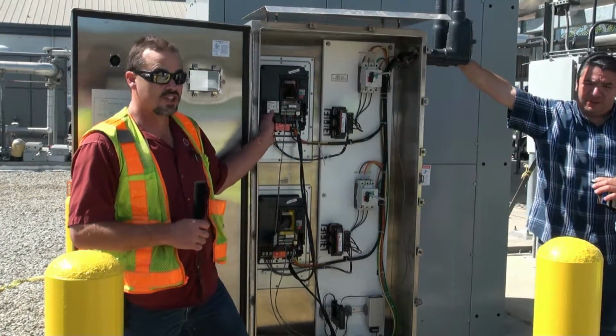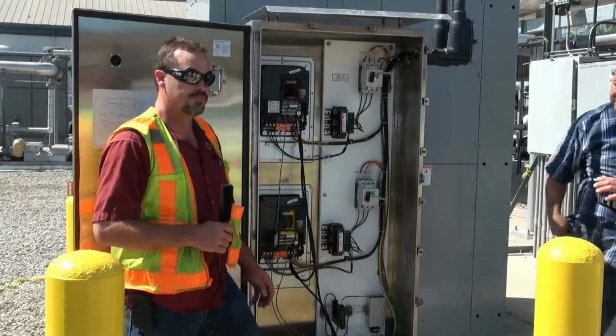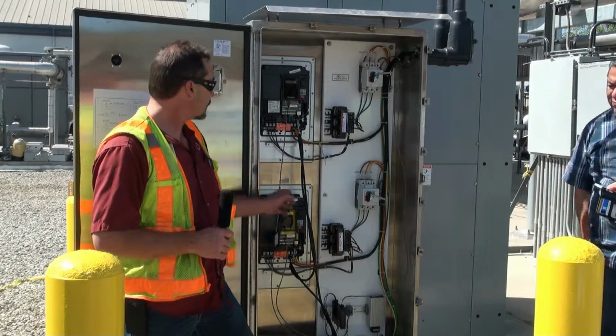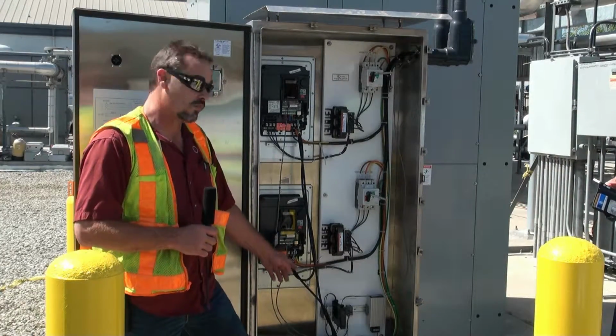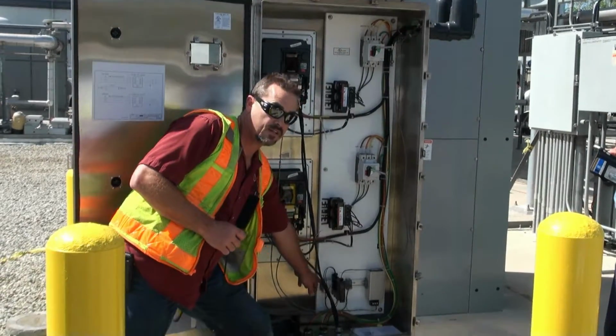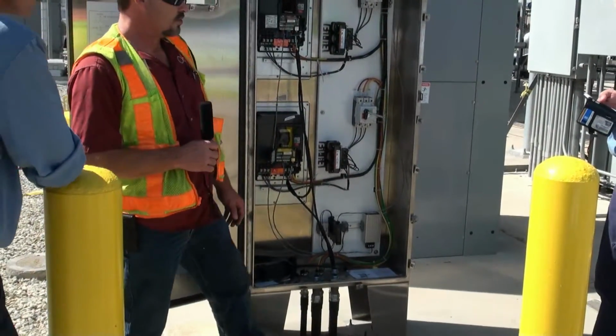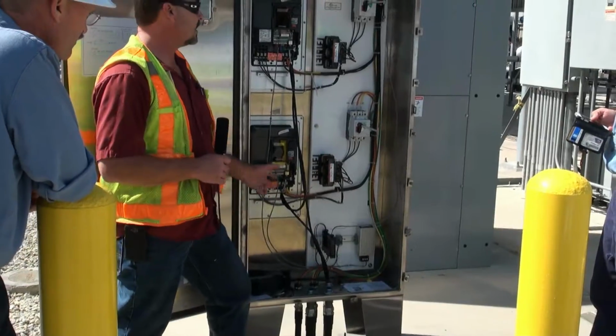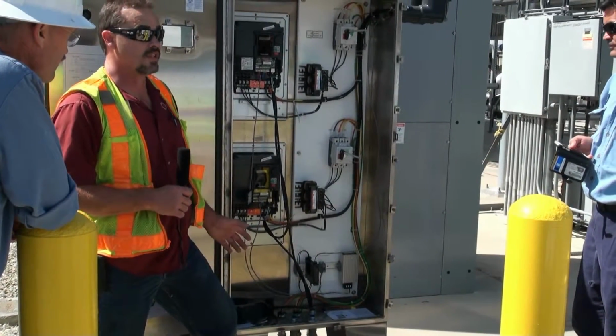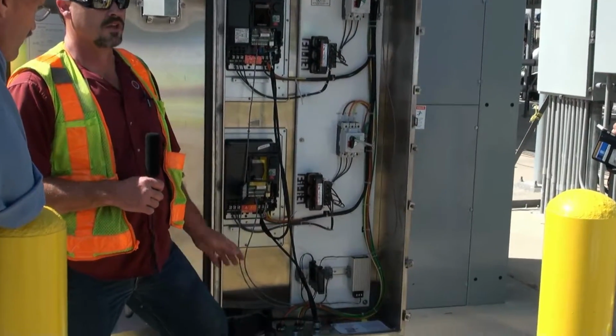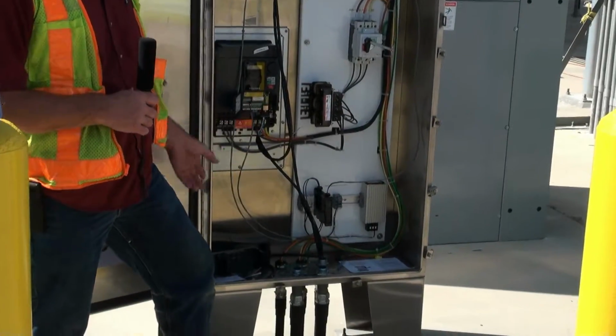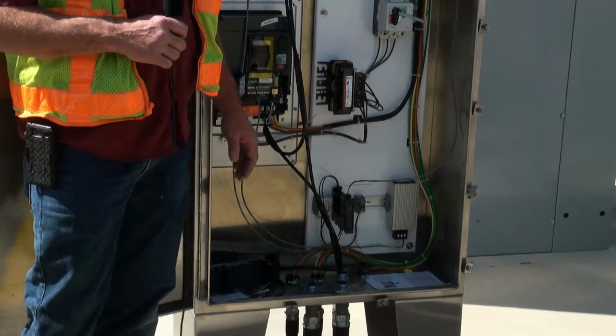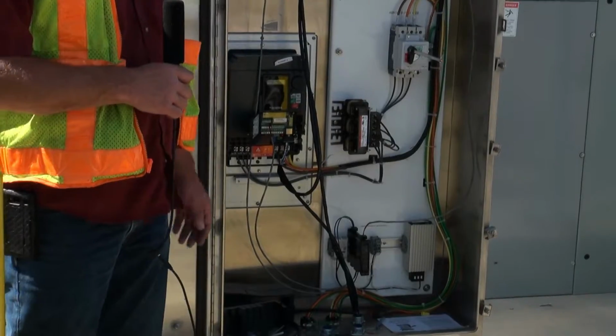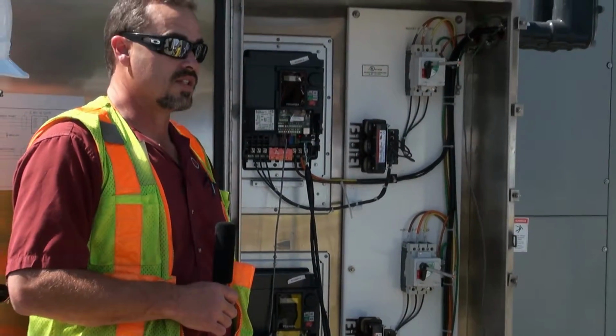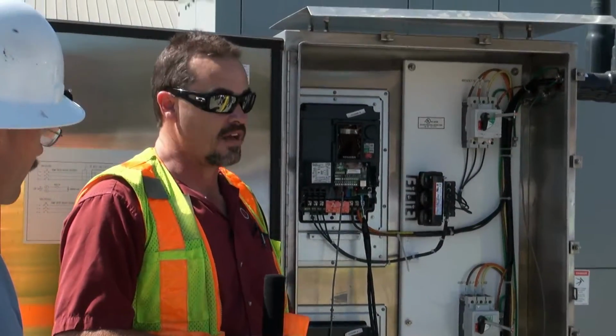Okay, so these are the Toshiba drives that we were talking about earlier. What we have to start with is we have a temperature sensor down here. Usually you want to have that set to around 90 degrees. You don't want to go over that because in the mornings, if it turns on and it's pulling cool air in with moisture in it, you don't really want that coming in. So 90 degrees is a good set temperature for it, maybe 85.